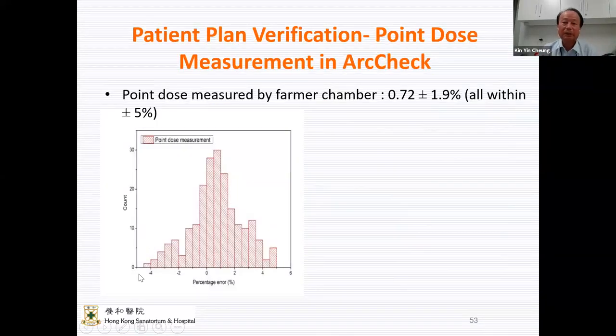And these are typical data that we get for our plans. For those measurements, our plans are well within tolerance: the mean is 0.7% with 1.9% standard deviation. And this is the kind of dose distribution error. So no data is worse than 5%. Most of them are well within 4%.